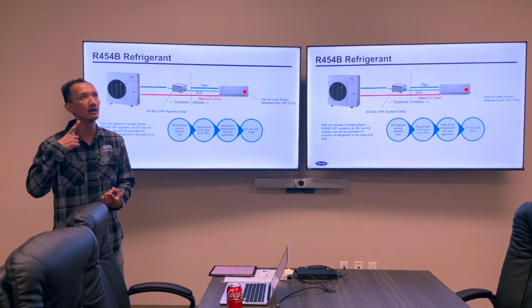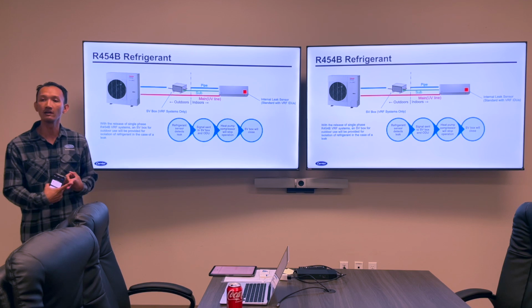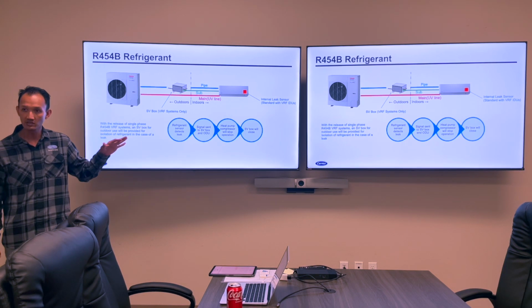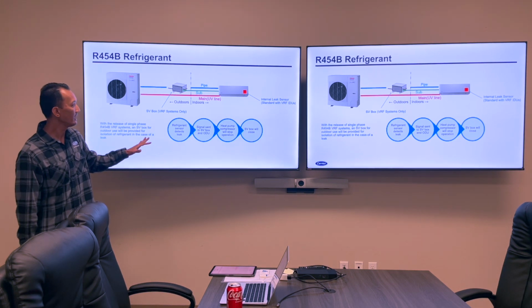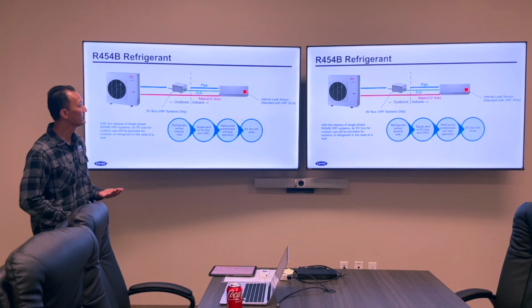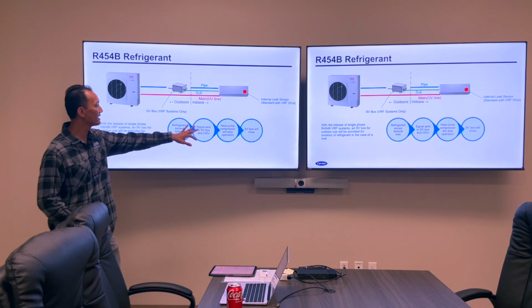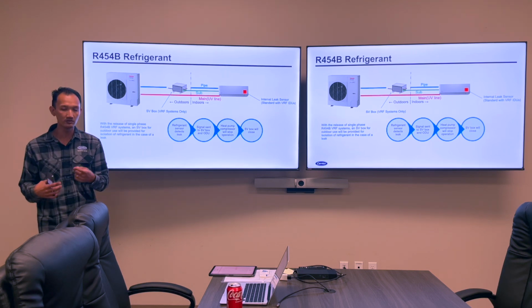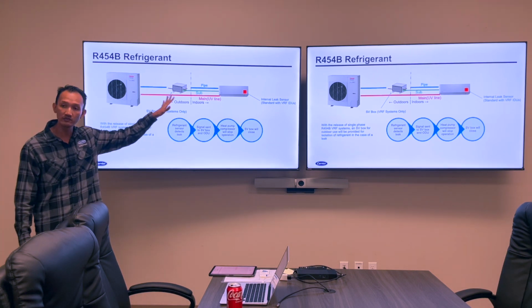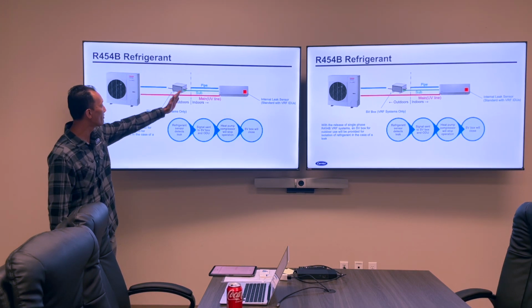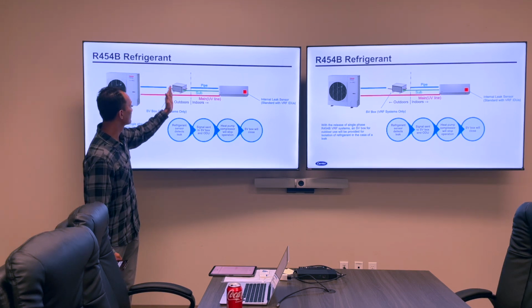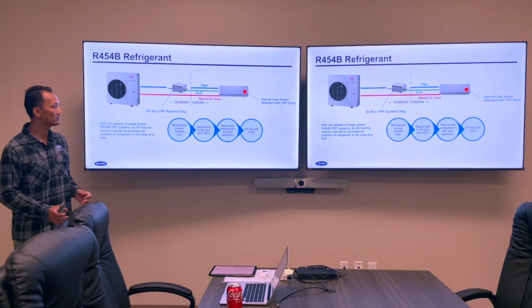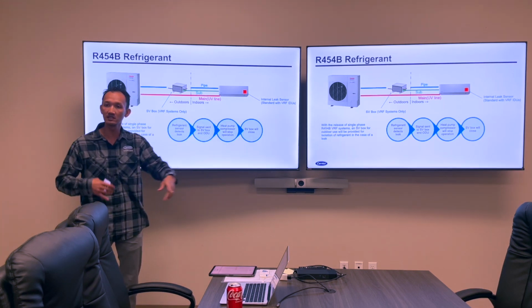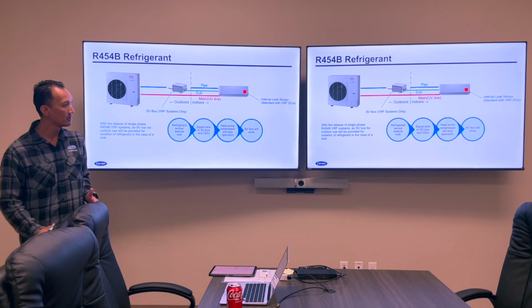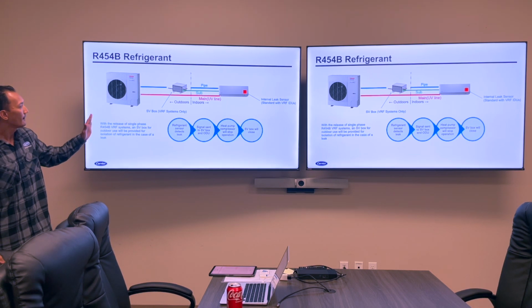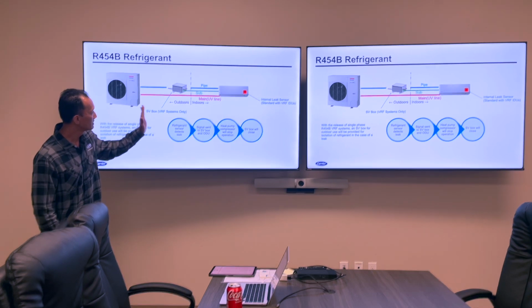Like I said, we have leak detectors on all of our fan coils, so that's already built in. And we have the logic built in to our system. And this is how the control logic would work if the sensor detects a leak. It would tell the outdoor unit to shut off its compressor so it's not sending more refrigerant into the system. It would tell the SV box to close its valve. So any refrigerant from the box to the outdoor unit gets cut off and it potentially does not leak into the space. And then it will tell the fan coil to continuously run its fan to help dissipate the refrigerant in a space. Yeah, so that's how that works.